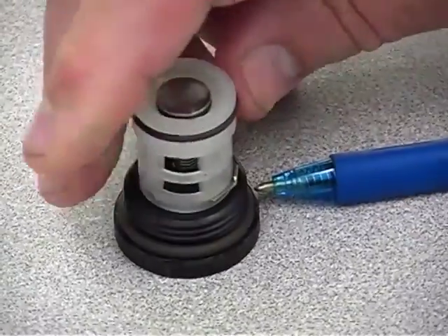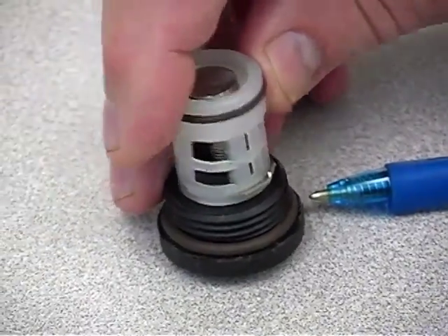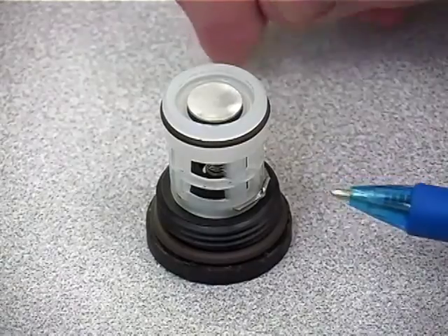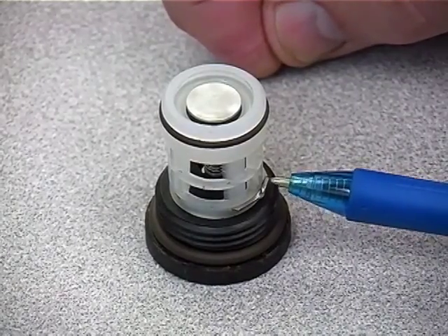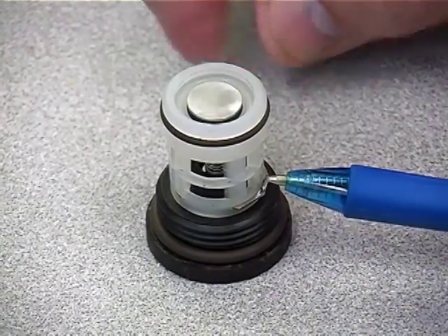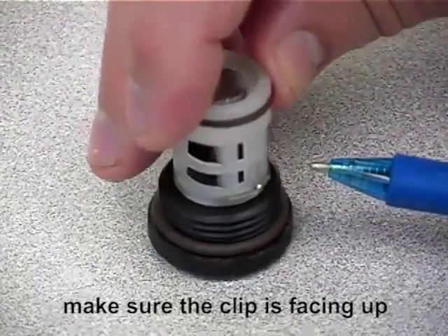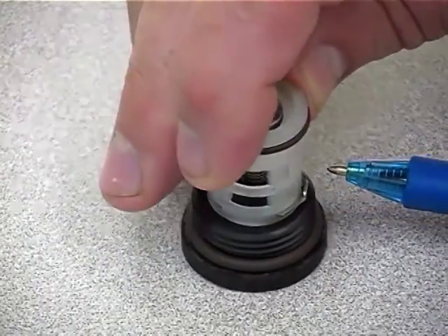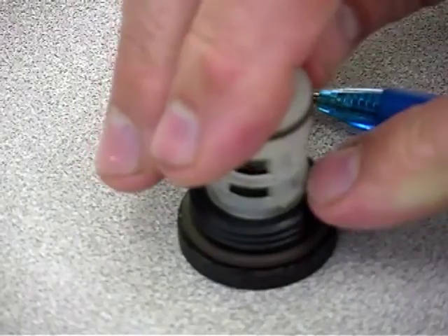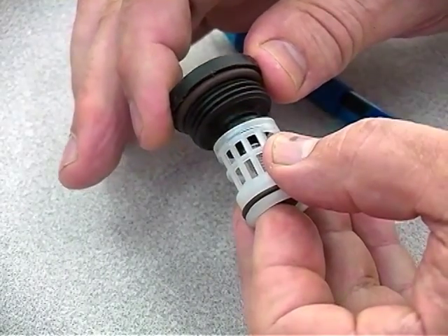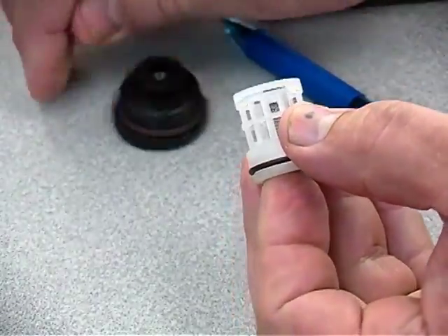If you look right here, there is a little clip that holds the valve body to the neck of the valve itself. There's a little tab on this clip, and you see that? We always want that facing up. Everything is spring loaded, so be careful when you take these apart. We always recommend taking them apart inside a clear plastic bag. That way parts don't fly all over.